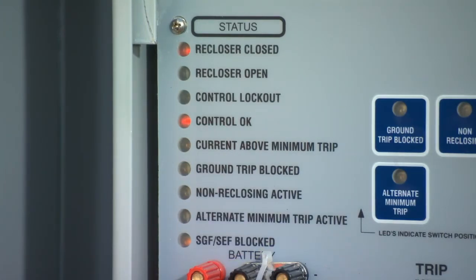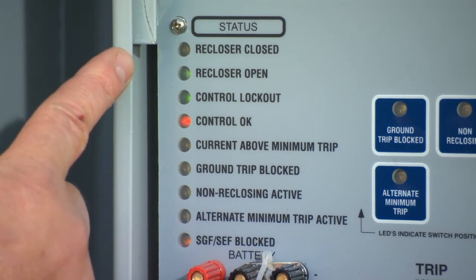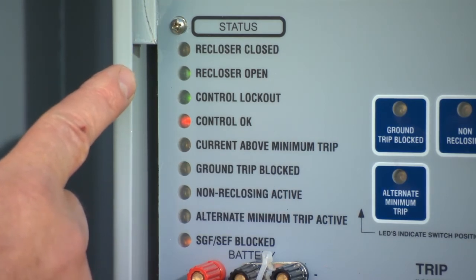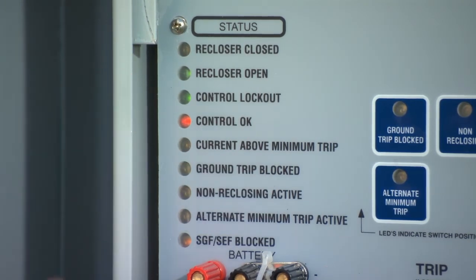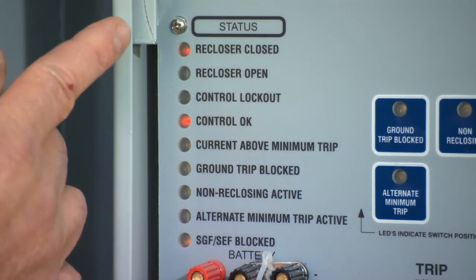After pressing the trip button, you will notice the recloser open and control lockout indicators are now green. Pressing the close button will close all 3 phases, causing the recloser closed indicator to turn red.